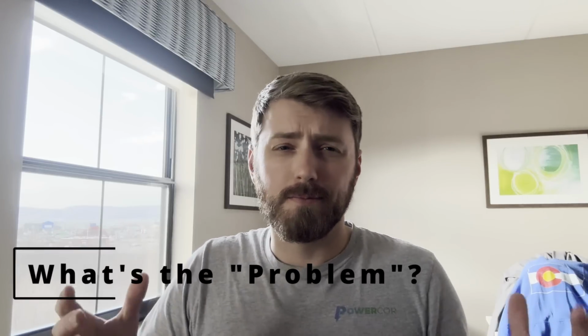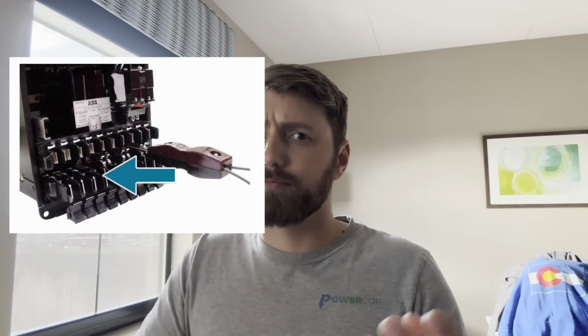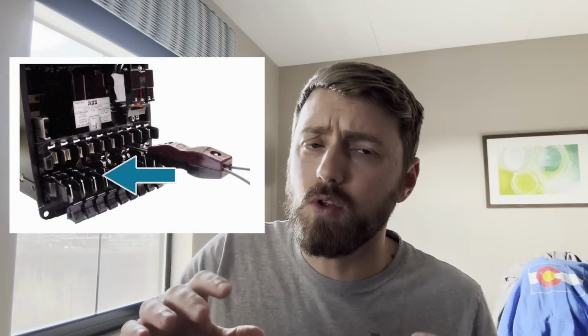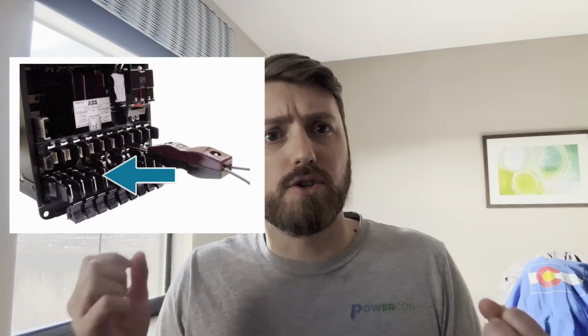Well, some maybe well-intentioned engineer in the last decade or so, sitting in an air-conditioned office, thought: if the PTs are connected to the blade side, when you pull the blades out to isolate it, you've got an exposed, energized conductor that could shock somebody, or short it and blow the PTs. If this engineer had ever tested relays or spent any time in the field, he'd know the test switches have to be that way.